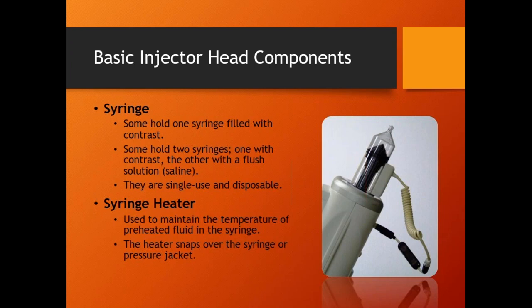exception to that. The ACIST uses their syringe 5 times. But the way the ACIST CVi works, they don't actually touch anything when they're filling it. It refills itself automatically, so they can use the same syringe all the time before they pitch it. But yeah. Now, what I tell my students though is, now that you know how to do PMs on these, you need syringes when you go PM. You don't use your syringe once and toss it. First time you go do a PM on the Stellant, ask the department for 2 Stellant syringes. Now those are your PM syringes. You'll keep those. They'll last you dozens and dozens of PMs. All right. And then last thing, the syringe heater. This is a picture. That's actually my Stellant right here, and that's just the syringe.